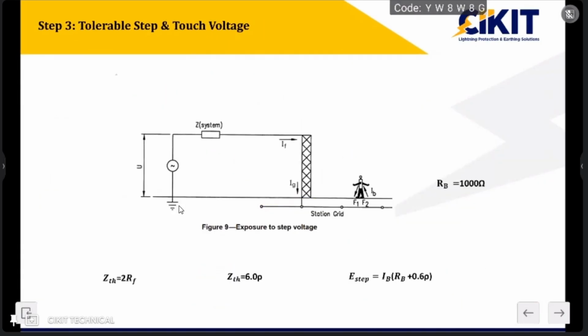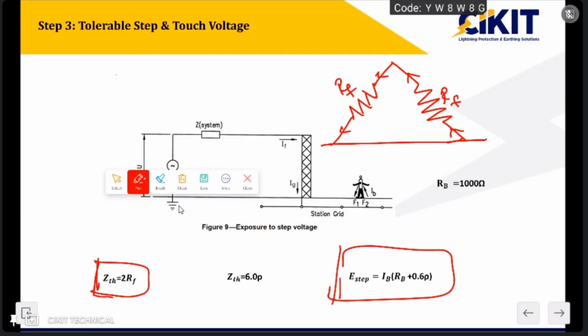The touch voltage formula will be IB into (RB plus 1.5 rho). If I am going for the step voltage, there is no direct contact and the current is flowing from one foot to another foot. So if one person is standing like this, RF is the foot resistance, and the current will be flowing in this loop. In this case, the two RF are considered as a series connection, so Z terminal will be equal to 2 times RF. In the previous case, for touch voltage, the two resistors were connected in parallel, but here they are in series, and the step voltage formula will be IB into (RB plus 6 rho). Using this formula, we can calculate the step voltage.